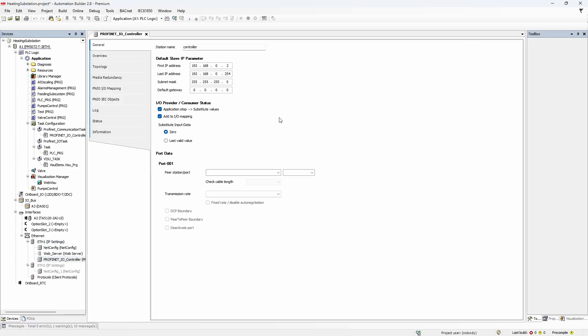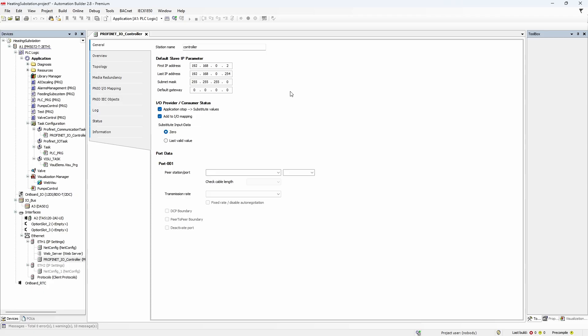Go to PROFINET I.O. controller settings. Now we don't need to set up PROFINET I.O. controller IP address because we use Ethernet port which already has IP address assigned 192.168.0.10. But what we need to do is to specify IP parameters which will be assigned to PROFINET I.O. devices like CI501 when controller establishes connection to them. Like, what's the range from which IP address will be taken?